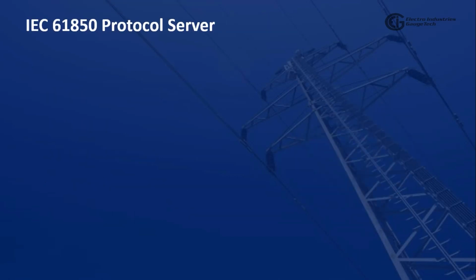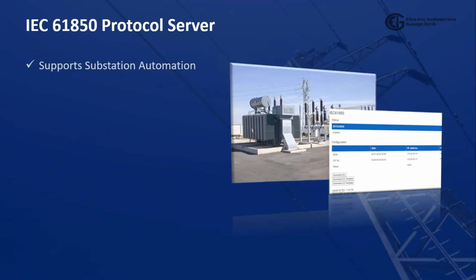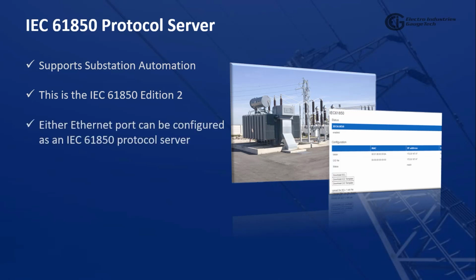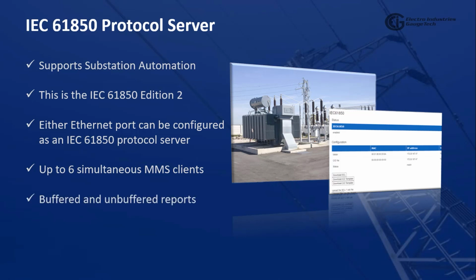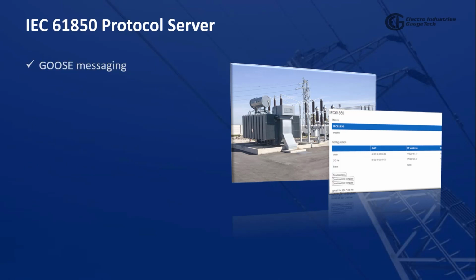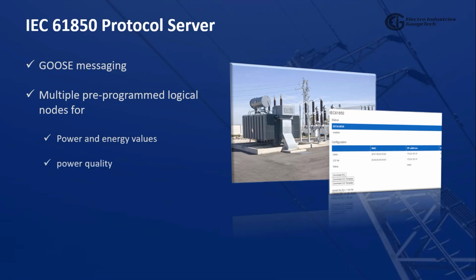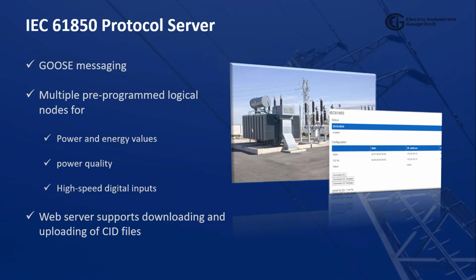Next feature is the IEC 61850 protocol server, which supports substation automation. This is the IEC 61850 Edition 2. Either Ethernet port can be configured as an IEC 61850 protocol server. Up to 6 simultaneous MMS clients, buffered and unbuffered reports. GOOSE messaging, multiple pre-programmed logical nodes for power and energy values, power quality, and high-speed digital inputs. Web server supports downloading and uploading of CID files.